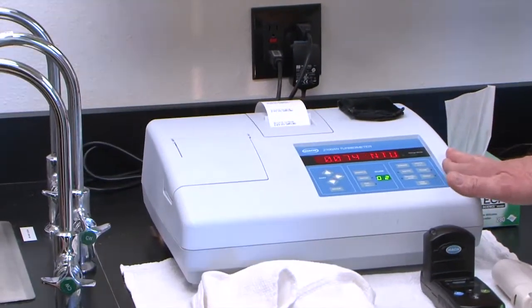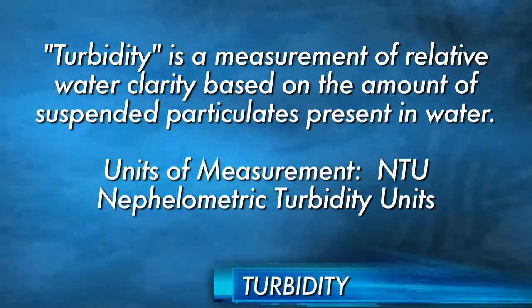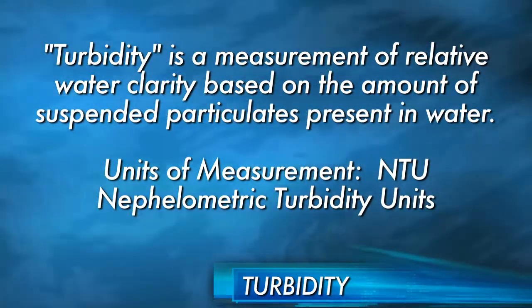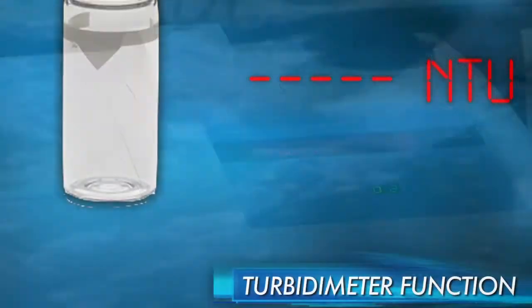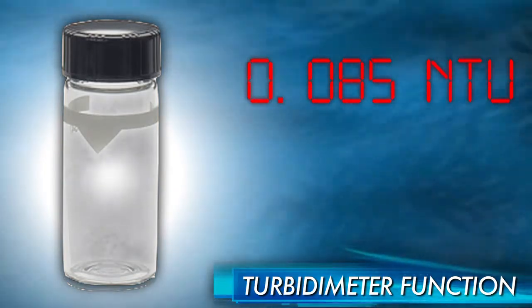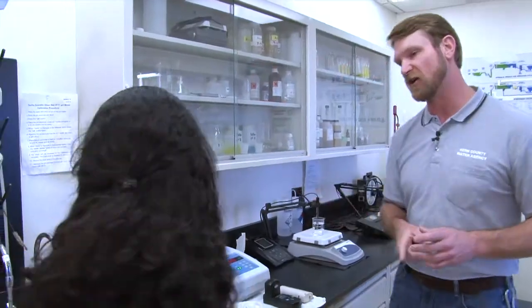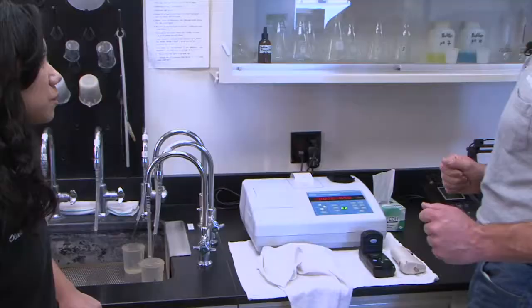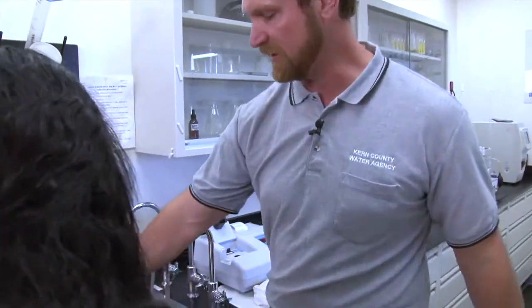The last test we're going to show you is turbidity, tested in NTUs — Nephelometric Turbidity Units. That's a big word, but basically all it means is the clarity of the water. How clear is it? Is it really cloudy or is it easy to see through? The machine shines a light through the sample and gives you a numerical readout of exactly how clear the water is. We'll do a test on our raw incoming water and then on our outgoing water. We take our little vial and dump the old sample out.